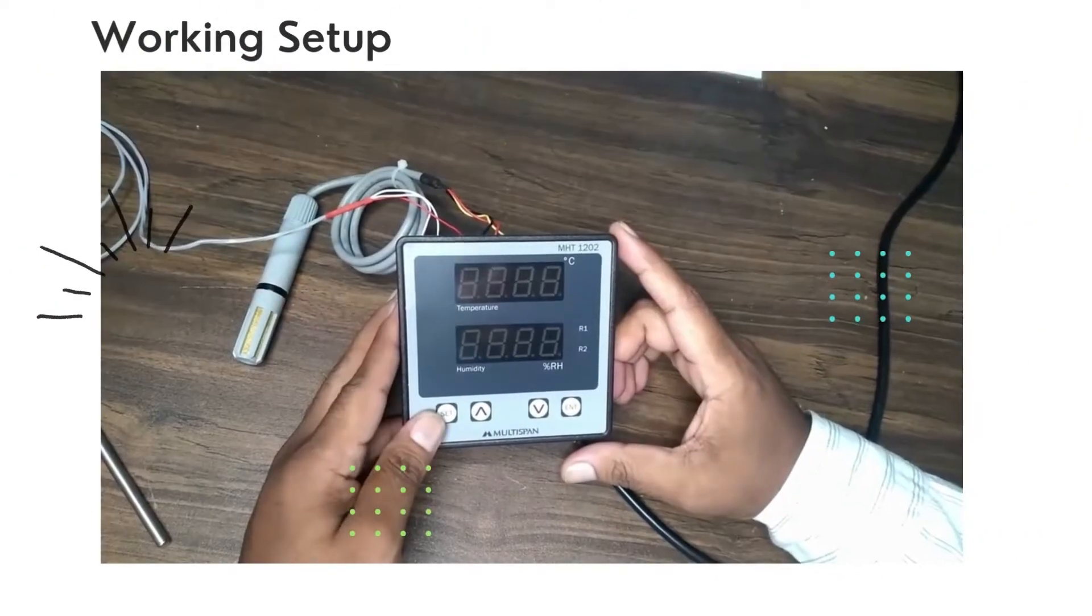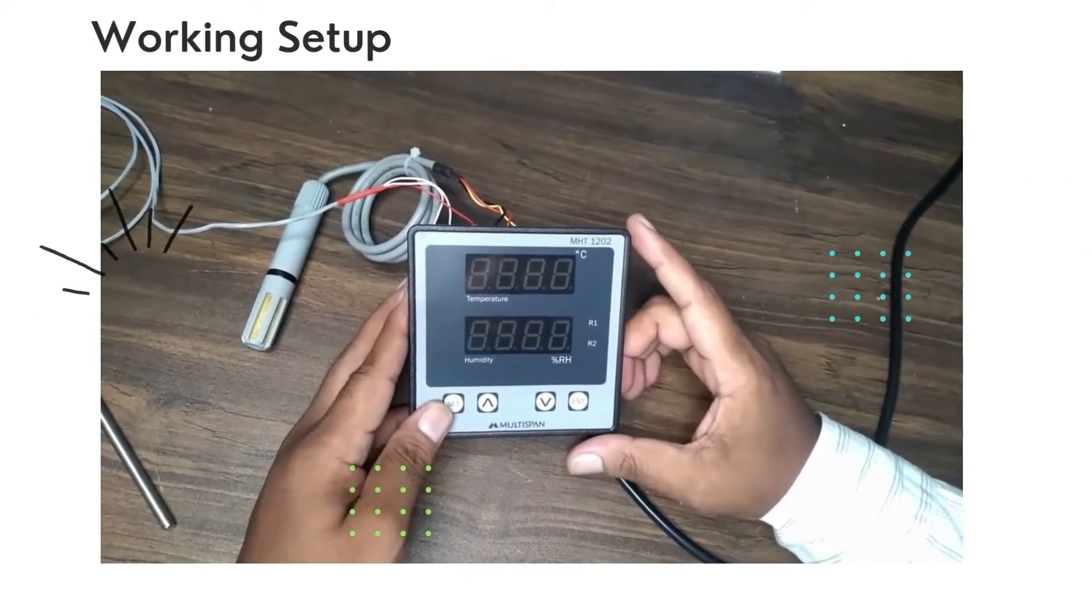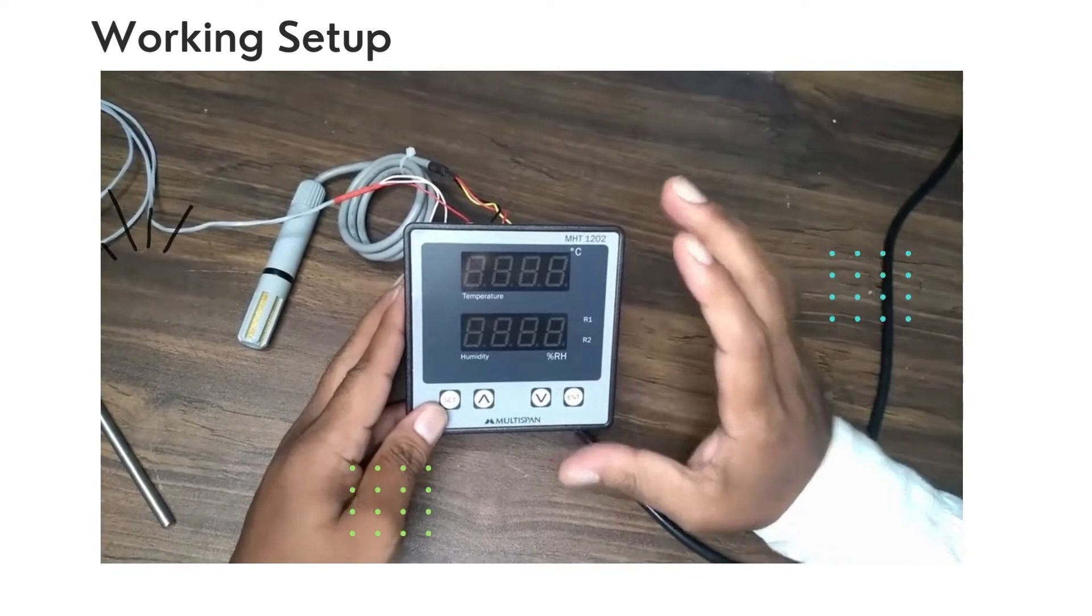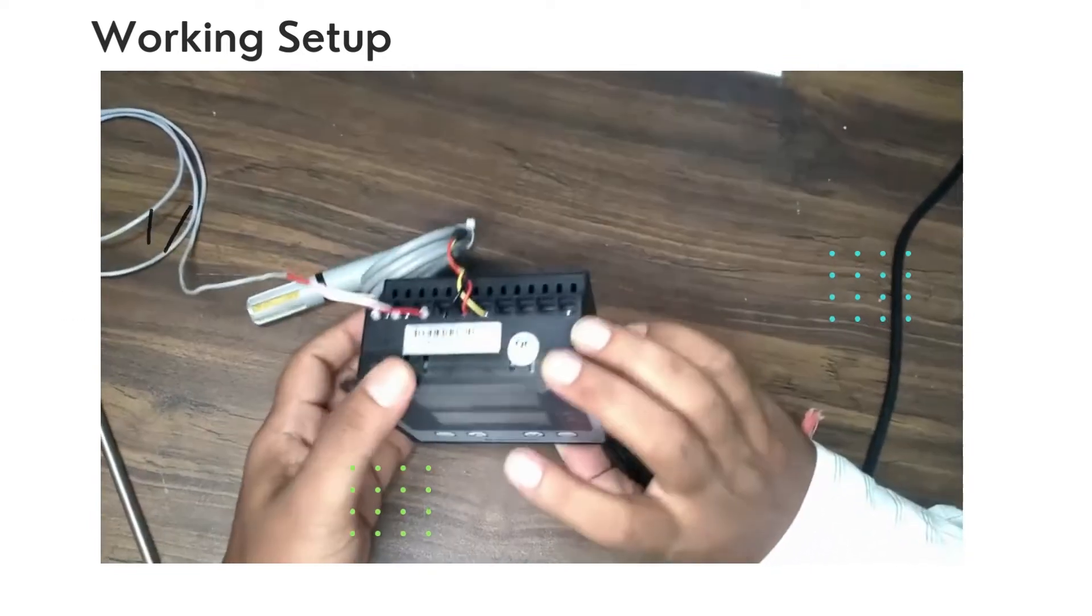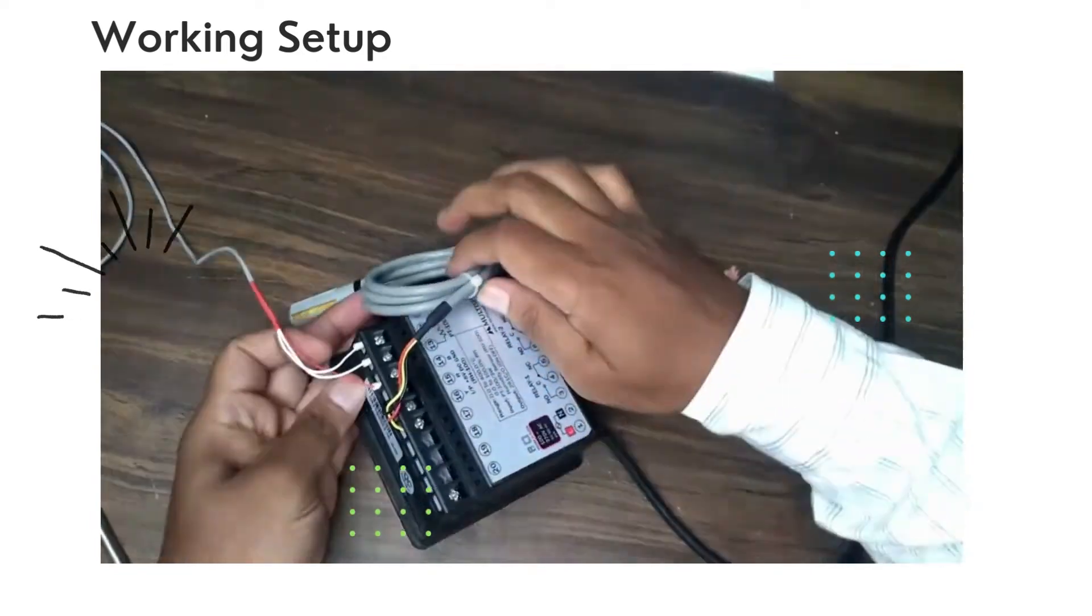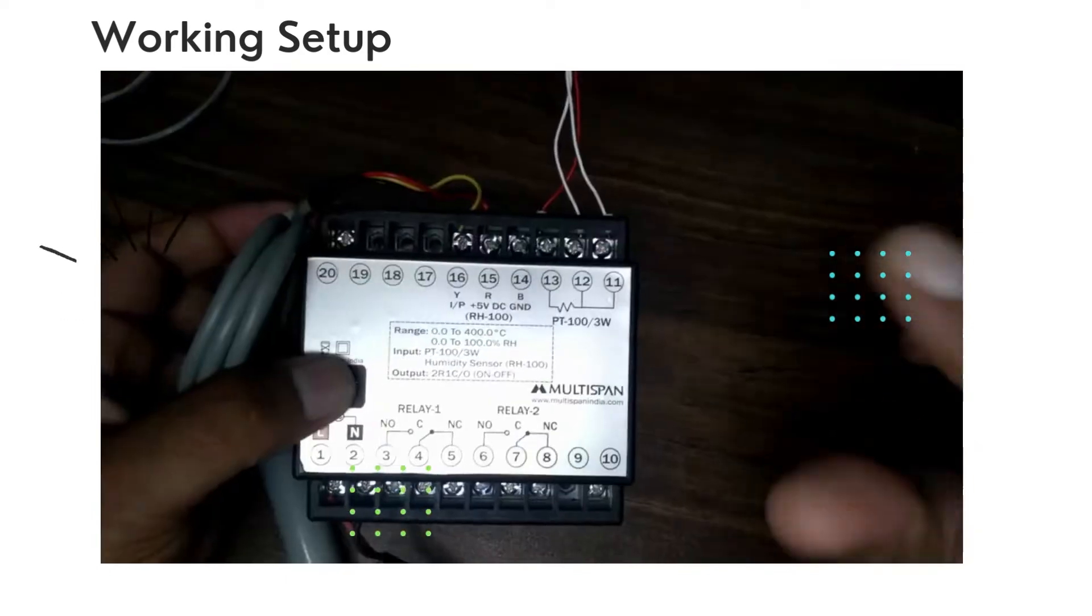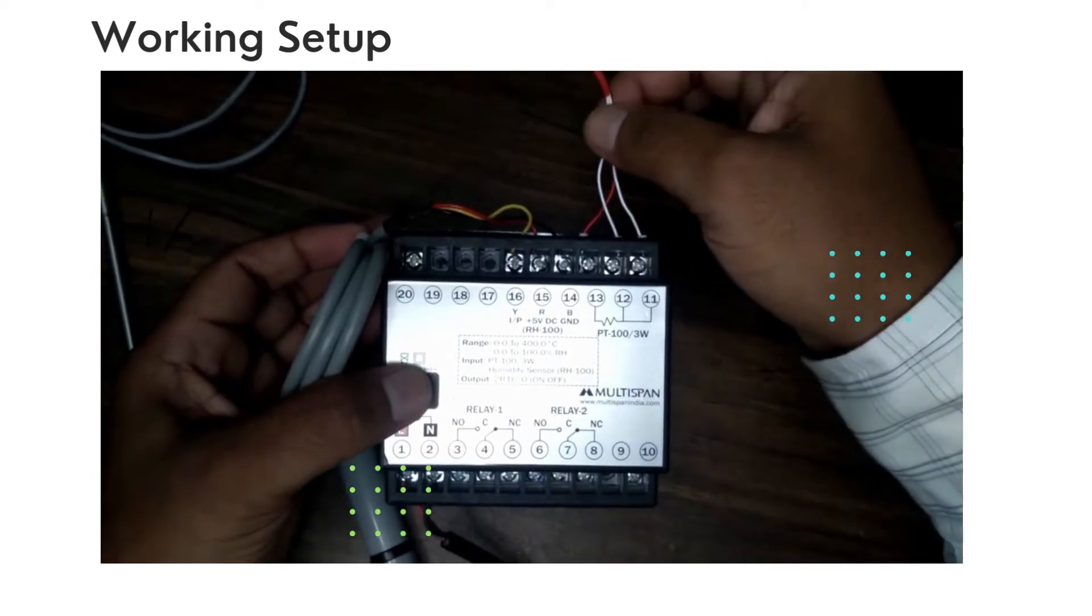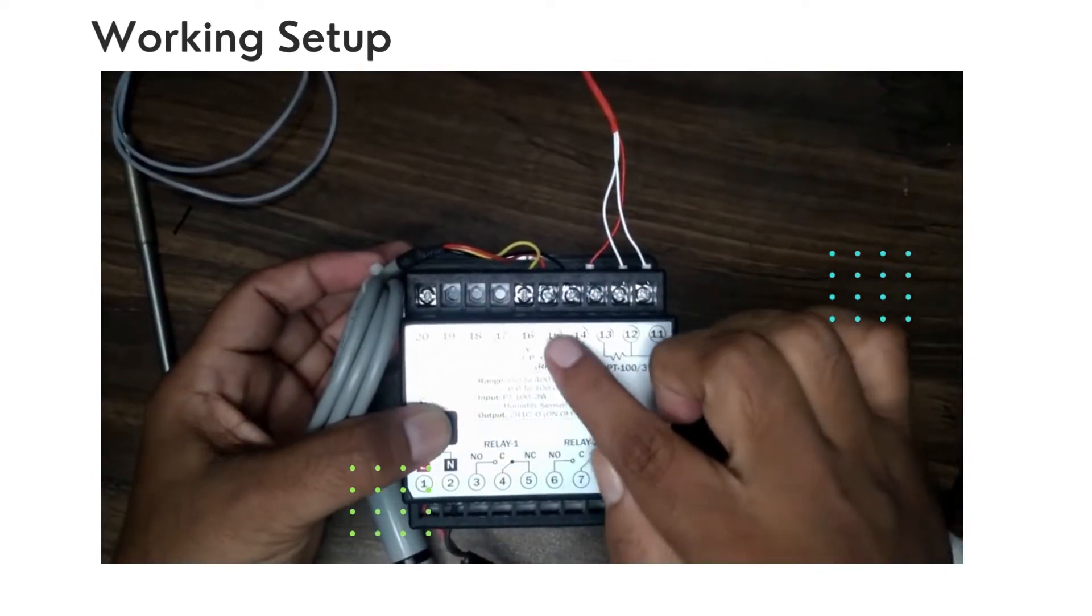This is our Multi-Span model MHT-1202, a temperature and humidity controller. We have done RTD temperature sensor connection over here. Terminals 11, 12, and 13 are for PT-100 connection, and 14, 15, and 16 are for the humidity sensor.